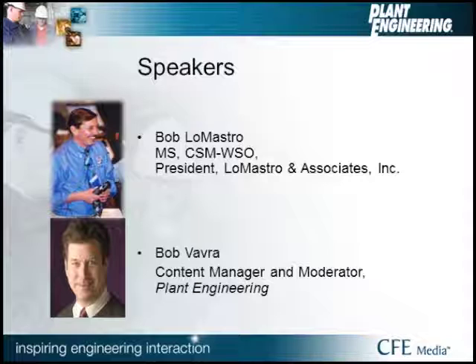So, another question: are sub-panels likely to have an arc flash event as compared to a primary panel or a switch? They can have arc flash events. The sub-panels have lower incident energy generally. But that doesn't mean that anytime we're creating an arc by opening and closing contacts or making contacts with leads, if you bring conductive tools or equipment inside that space, the risk of arc still exists. It's just minimized by the level of incident energy.